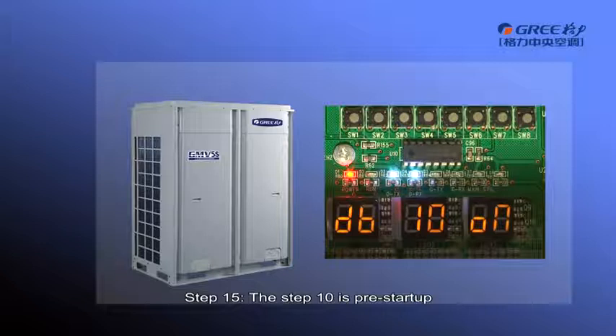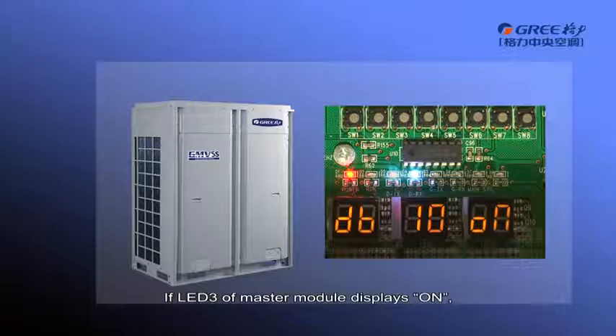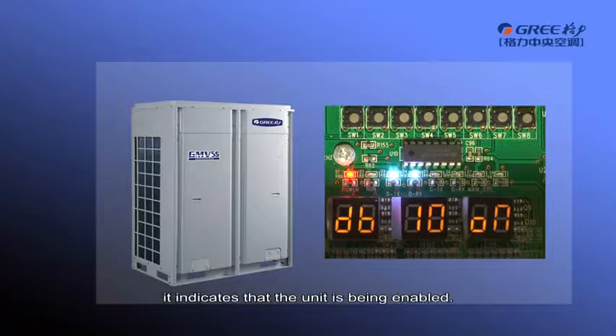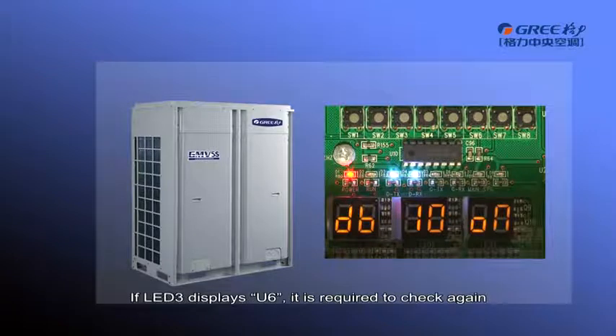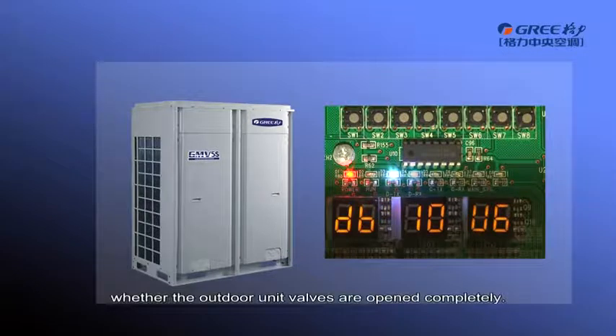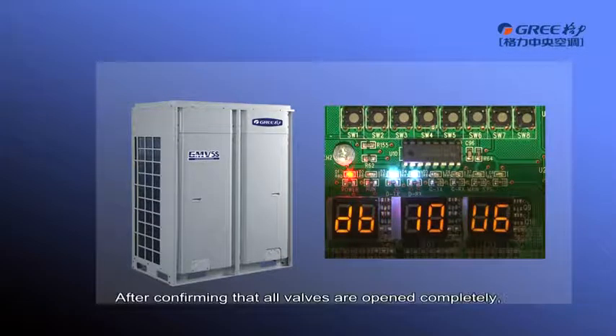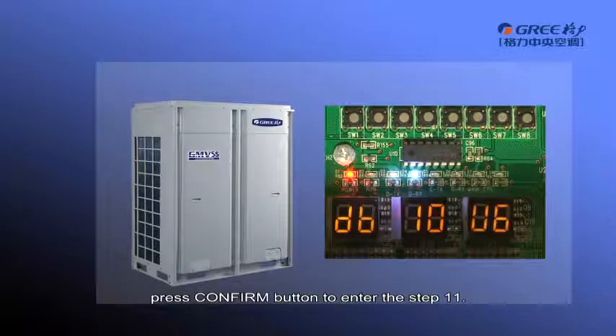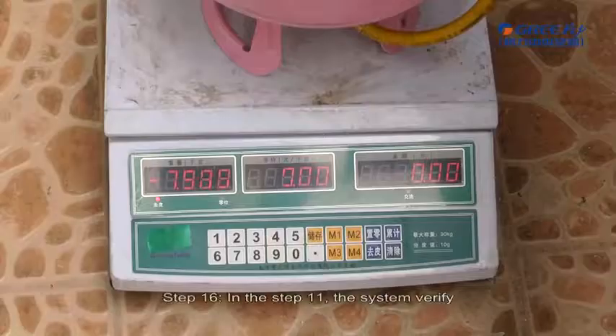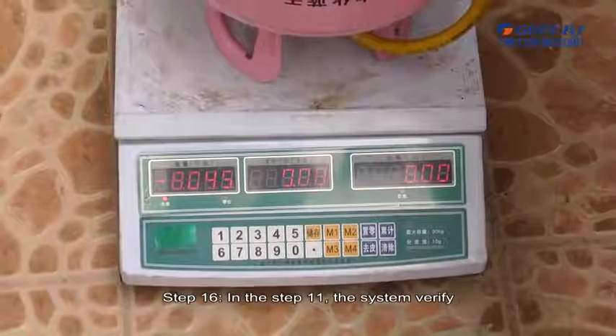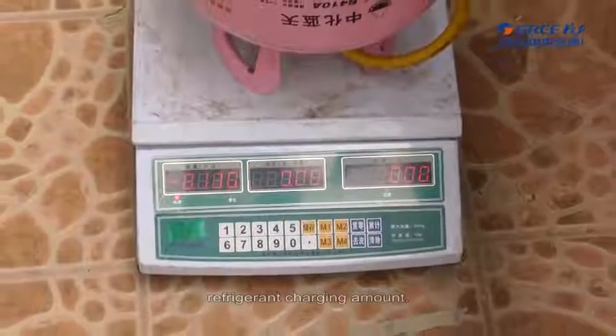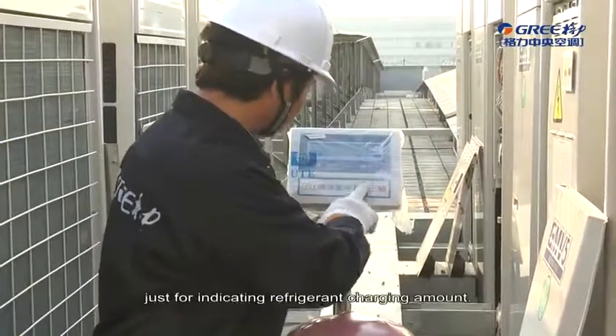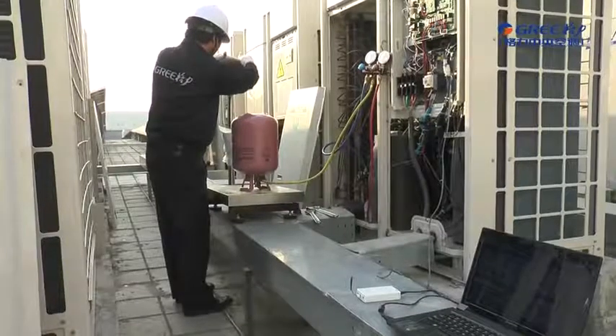Step 15. The Step 10 is pre-startup outdoor unit valve status detection. If LED 3 of master module displays on, it indicates that the unit is being enabled. If LED 3 displays U6, it is required to check again whether the outdoor unit valves are open completely. After confirming that all valves are open completely, press Confirm button to enter the Step 11. Step 16. In the step 11, the system verifies refrigerant charging amount. This step needs no operation, just for indicating refrigerant charging amount.